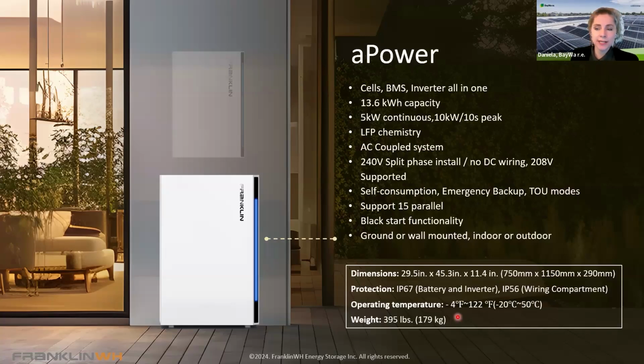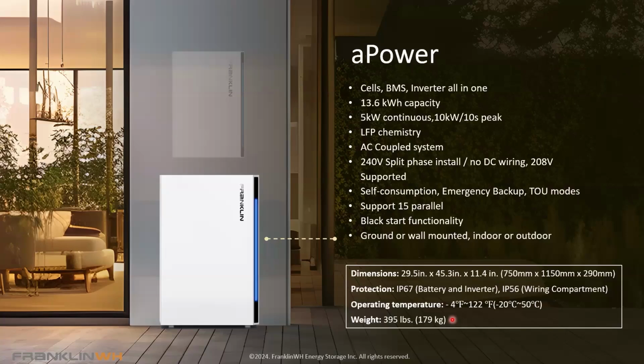What if a legacy PV system already has batteries, SolarEdge inverters, LG Chem batteries? That's a great question. We do have a number of systems in the field where we've retrofitted those types of legacy DC coupled systems. I have a number of single line diagrams I can supply if they would like. You can contact me or engineering at FranklinWH and we'll provide those. Essentially, they would be connected to the PV input, and you would be limiting a little bit of the capability of that legacy system because it would only be outputting as basically PV only. You would be moving your backup circuits downstream of the Franklin system. But again, there's about 4 different configurations for integrating with those hybrid systems. So I can provide more detail. And if there are nuanced questions, again, we have our engineering at the FranklinWH.com support email or my contact directly.